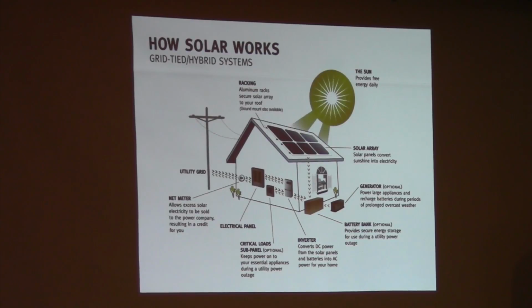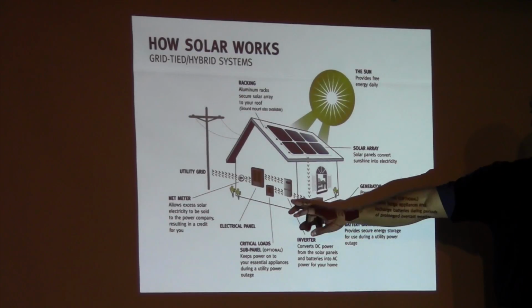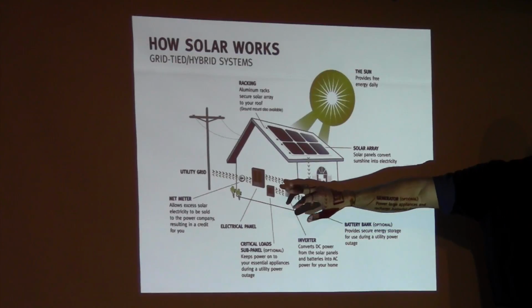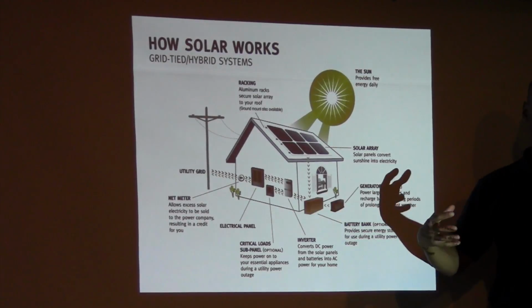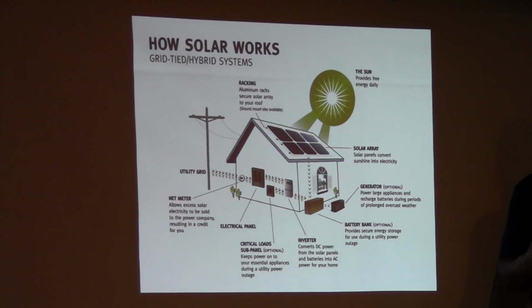Now how would that be connected through a transfer switch, from your generator to the main panel? You're talking about two different systems, correct? Yeah. So there's what's called hybrid inverters, which act as a 4-way transfer switch: you have AC from the grid, optionally AC from the generator, DC from the battery, and DC coming in from your solar panel array. That inverter can switch between, or even run multiple of those power sources concurrently, based on how you program it.